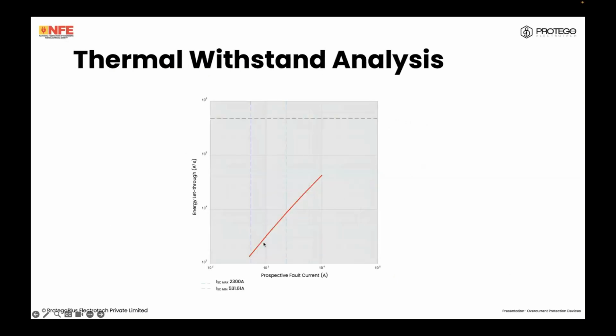Now, we'll go on the graph. The purple line denotes the minimum fault current, which is our 531.61, which we just calculated. The blue dotted line denotes 2,300 amps, which is our maximum fault current at the point closest to the commencement of supply. The black dotted line denotes this value, 476,100. The red line is the let-through energy characteristic of the breaker. We need to make sure that for areas between the purple dotted line and the blue dotted line, the let-through energy given by the red line is always lesser than the black dotted line. This line shall always be lower than this line, which in this case is satisfied.